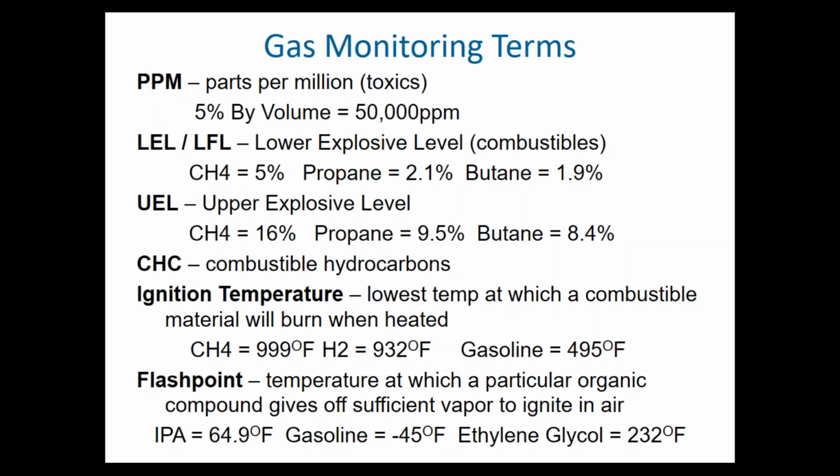I gave you the other examples. Propane is 2.1. Propane UEL is 9.5. You can see it's a smaller window. And butane is 1.9 to 8.4. Every gas has its own LFL and UEL.